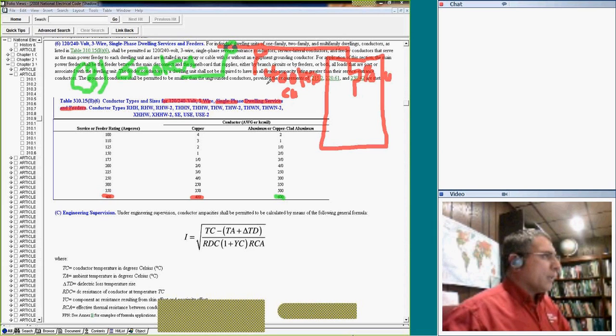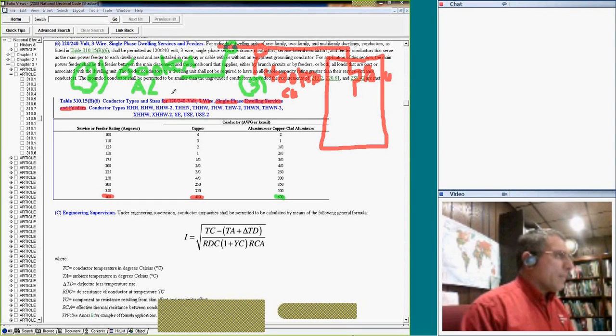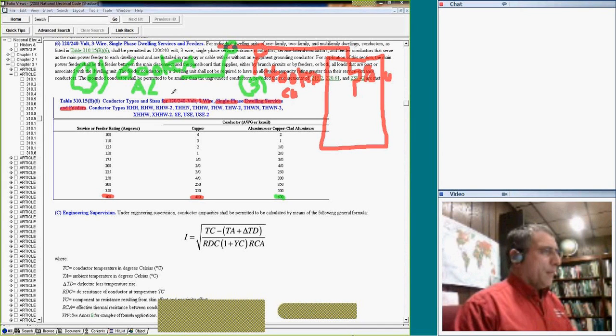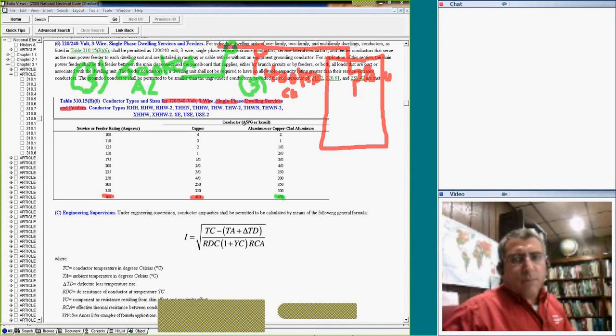There's a neutral calculation. So for practical reasons, let's say here are my 3 conductors, single phase. Remember, 2 hots and a neutral. 3 conductors, 2 hots and a neutral. Okay, may I ask you any question, guys, how to use this table? You need to know how to use this table.